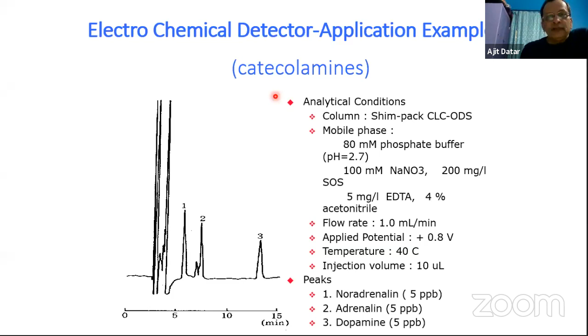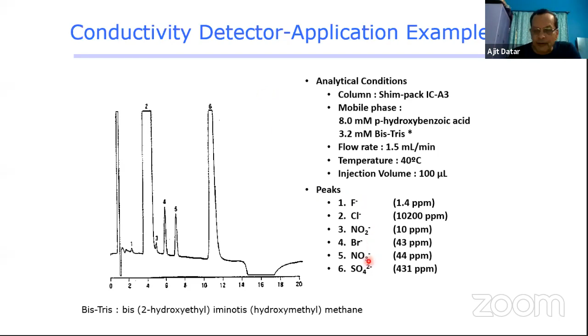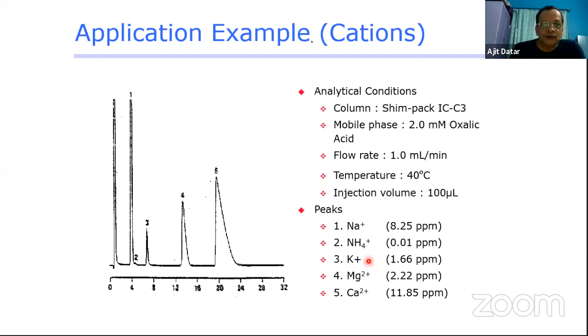This is a conductivity detector which is used with ion exchange chromatography. Here I have done separation of anions by using ion exchange chromatography with HPLC instrumentation, only the column being an ion exchange column. This is an anion exchange column. I have separated fluoride, chloride, nitrite, bromide, etc. This is a cation exchange column. With the same technique, I have separated sodium, ammonium, potassium, magnesium, calcium, etc. at ppm level. So this is ion exchange chromatography.